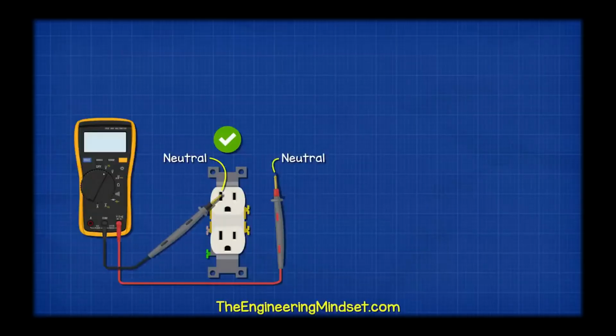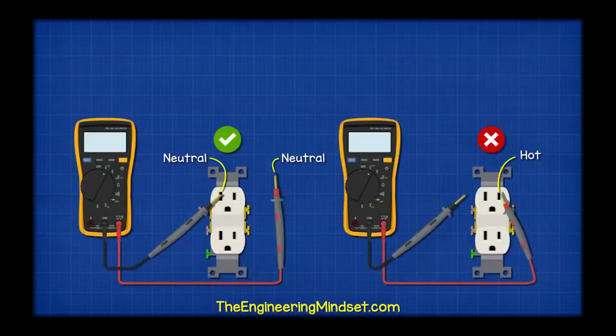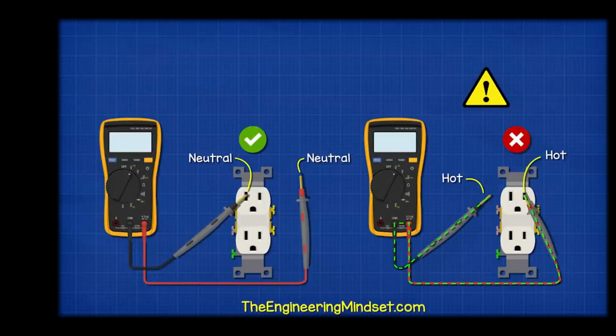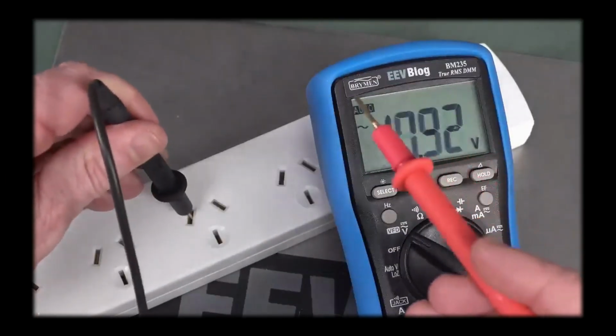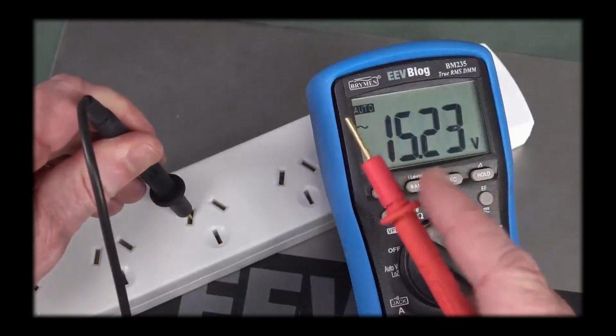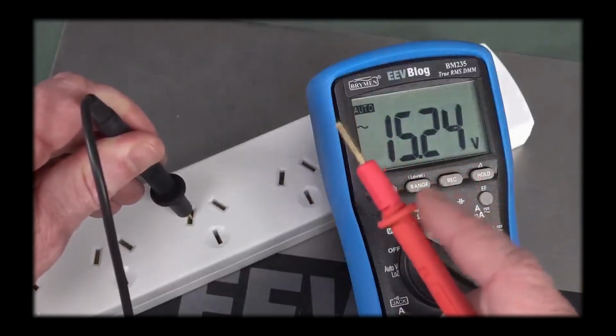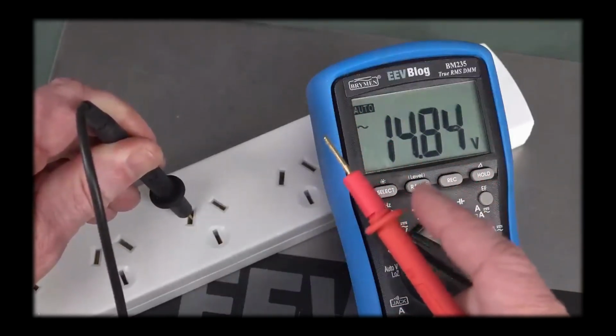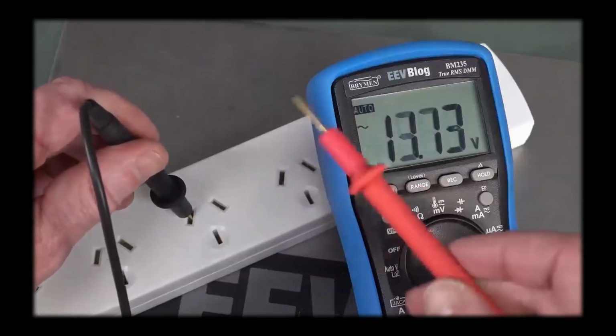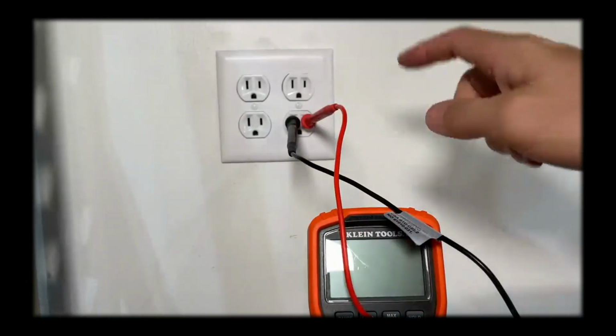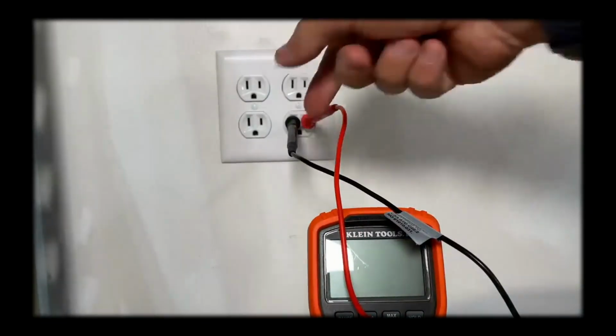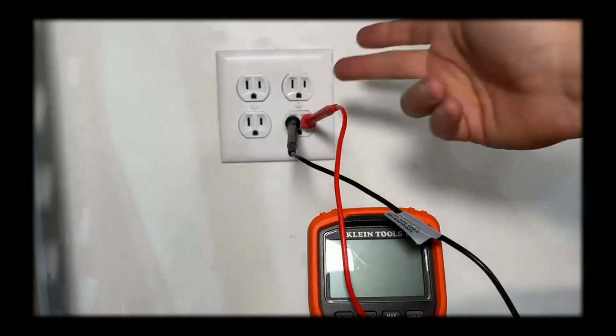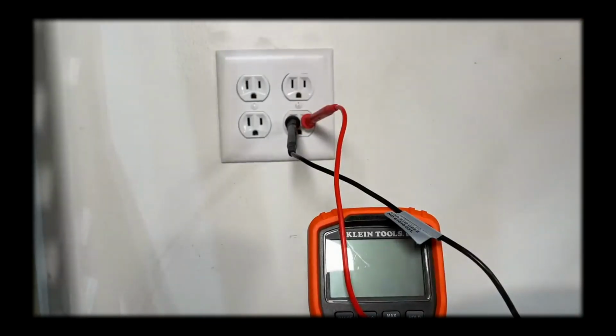Always connect the black wire to the neutral first, because if you connect the red wire to an active terminal first, the black wire will instantly become electrified. If you put one end in like that, the other end becomes live. So be aware of that, you might come a gutser and that'll ruin your day. Very dangerous. You do not want to start off with the red probe, or take out the black probe with the red still attached to the hot side.